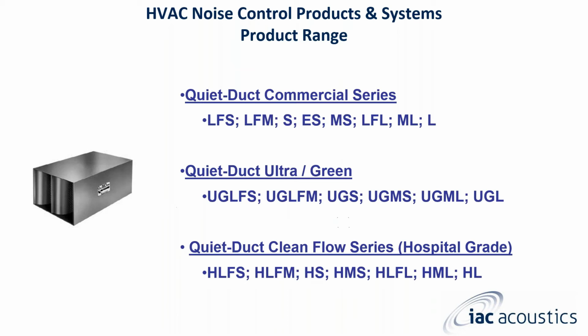Ultra Green is filled with the Ultra Green type material. It's 100% environmentally friendly material. It is 100% cotton. It is dipped in an antifungal, anti-mildew solution. And it's also green. I will say this: I have seen over the years that the Ultra Green silencers, UG-LFM, UG-MS, and UG-L, have actually outperformed the LFM, MS, and L of the Quiet Duct Commercial Series in the 36 and in the 60-inch ranges for lengths, in the neighborhood of about 500 to about 2,000 CFM. So take a look at that. It is around about a 5 to 7% adder, so to speak, because of the different infill material, but it does a really good job.